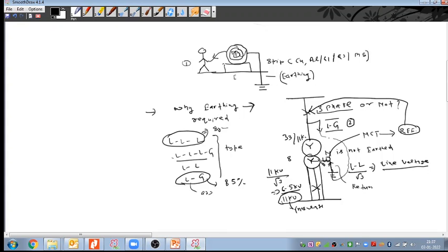So the system earthing, the neutral earthing, is for the equipment protection, and the earthing of the outer enclosure of the body is for human protection. That is not for the equipment protection. That is only for human being protection. This is for the equipment self protection. Neutral provides the return path.